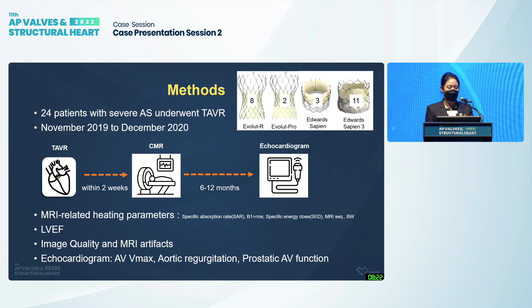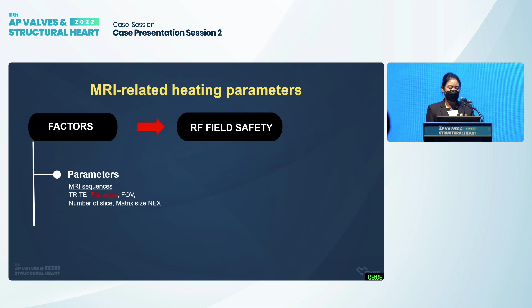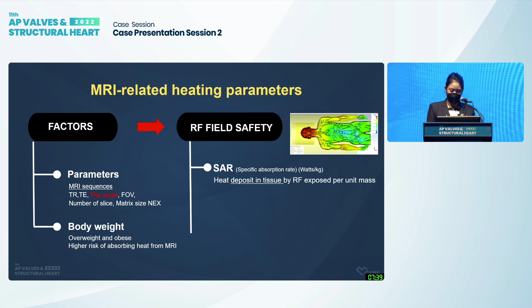So let me explain the MRI-related heating parameters. There are several factors that create heating in the patient. One is the parameter of the MRI sequence, and the second is the body weight of the patient. As we know, overweight or obese patients are at higher risk of absorbing heat from MRI. The heating parameters you should be concerned about are three. First is SAR, or specific absorption rate. This is the heat deposited in tissue by RF pulse, exposed per unit mass. It depends on the patient weight and the MRI sequence.